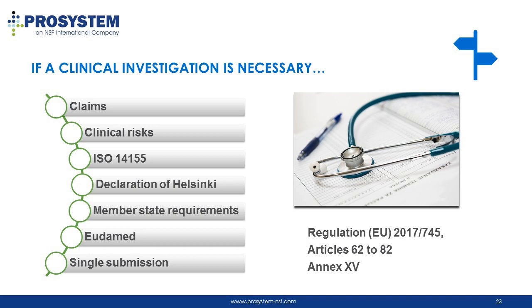You should also become familiar with further information on EUDAMED, the electronic system on clinical investigation in the European Union, and on single submission. Regarding the requirements on clinical investigation, I also would like to emphasize that they went from approximately 2 pages in the MDD to approximately 20 pages in the regulation, which include information found in 20 articles and 1 annex. Unfortunately, we do not have time to explore these topics in depth during this webinar, but I have indicated the respective articles and annex here for further reading.